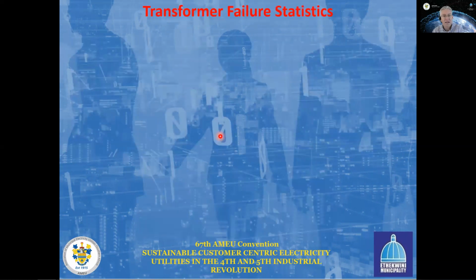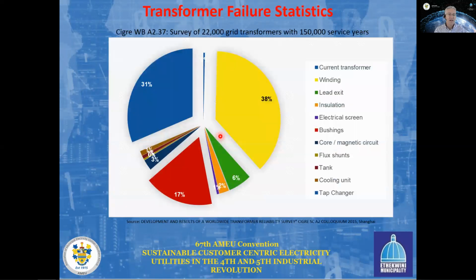So what causes power failures like this? There was an interesting survey done by Cigre a couple of years ago, in 2015, where they surveyed worldwide about 22,000 grid transformers with a total lifetime of 150,000 years. They categorized the reason why these grid transformers failed into all these categories that you can see on the right-hand side here. The three main areas that stand out are failures due to winding, 38%, failures due to the bushings failing, mainly the HV bushings, being 17%, and lastly, failures due to the tap changer. In total, about 86% of the failures of power transformers relate to the electrical or the active part of the power transformer, which means they could be prevented, or at least predicted, by suitable diagnosis and suitable testing techniques.